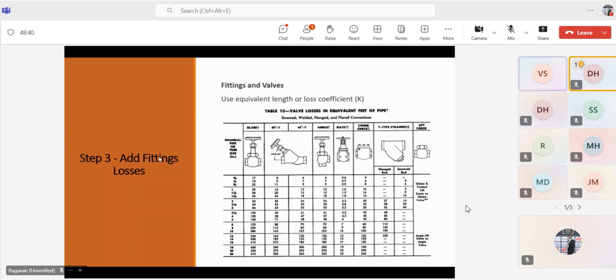Okay, then you can see here I added the valves and fittings data sheet. This is the manufacturer data sheet. Calculate the equivalent pipe length for fittings and valves using the ASHRAE guidelines or manufacturer data.